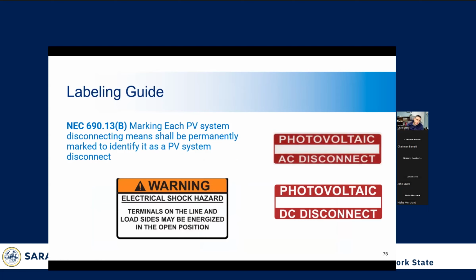The NEC also requires these markings right here on PV system disconnects. You have the PV AC disconnect or PV DC disconnect, obviously telling where the disconnects are. And they're red so that it's easy to see. And again, if you disconnect the system from the utility, the power's going to be off, but for a PV system, that's not necessarily the case.